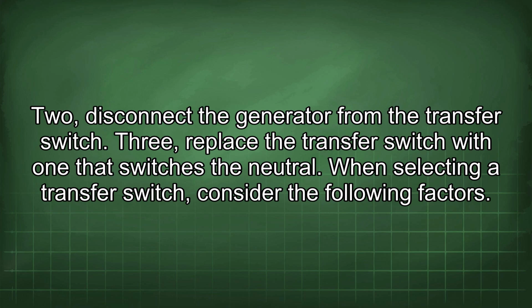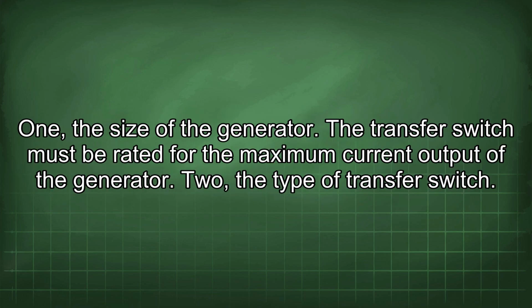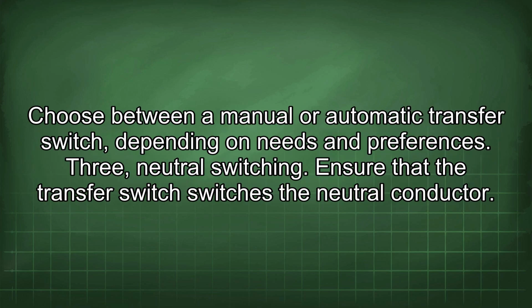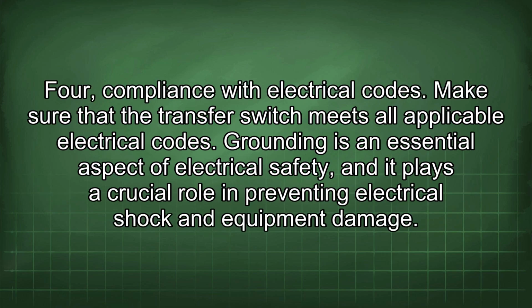When selecting a transfer switch, consider the following factors. 1. The size of the generator. The transfer switch must be rated for the maximum current output of the generator. 2. The type of transfer switch. Choose between a manual or automatic transfer switch, depending on needs and preferences. 3. Neutral switching. Ensure that the transfer switch switches the neutral conductor. 4. Compliance with electrical codes. Make sure that the transfer switch meets all applicable electrical codes.